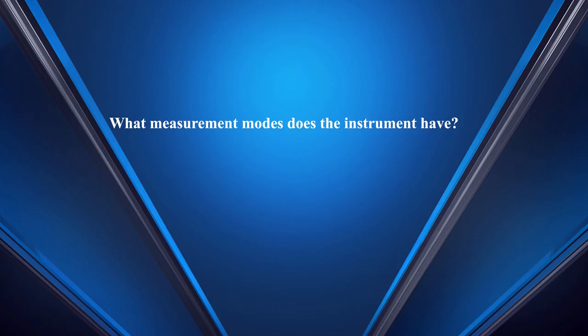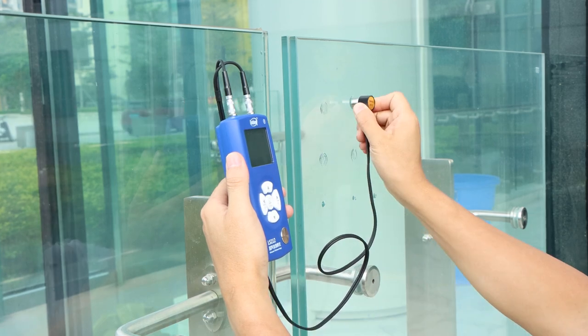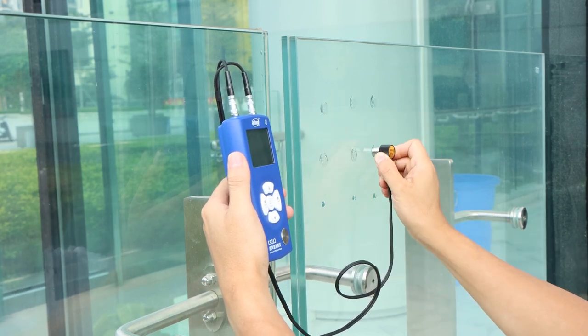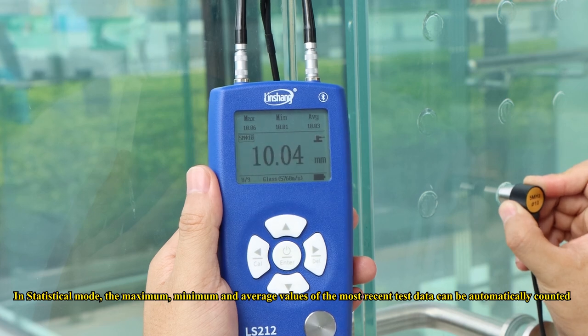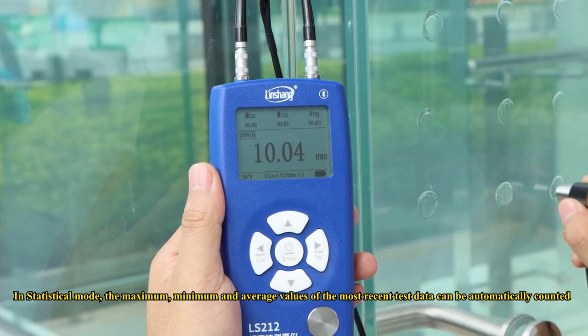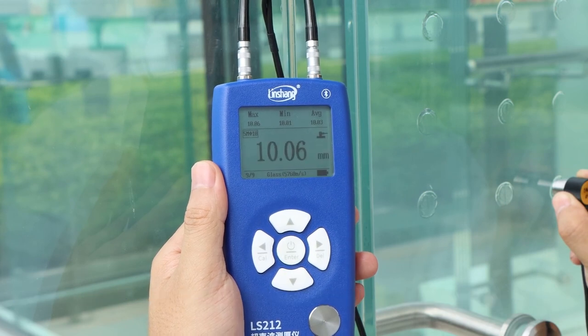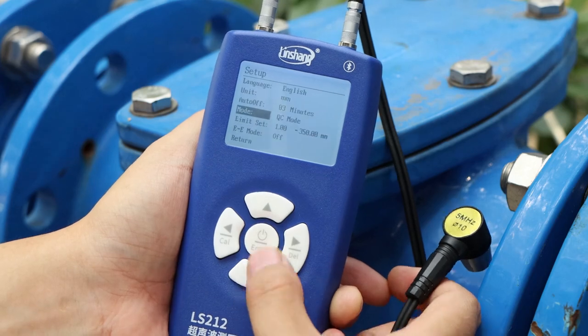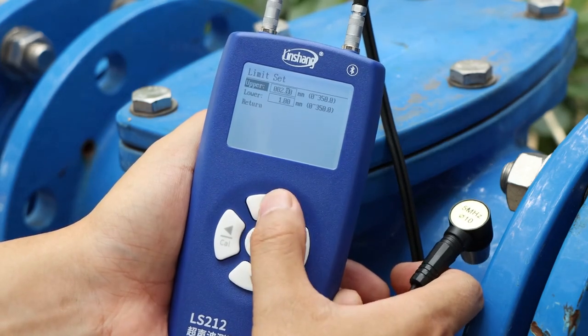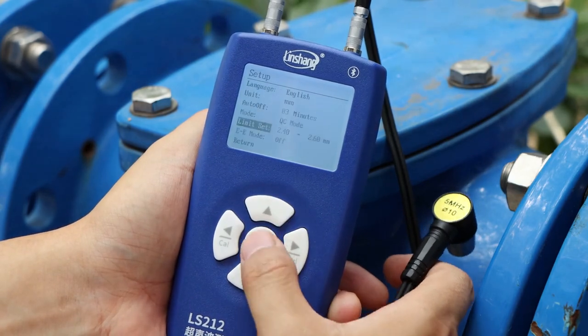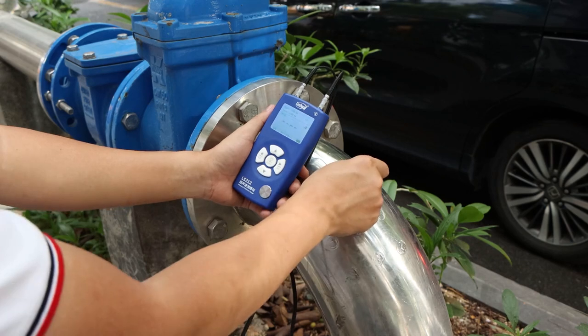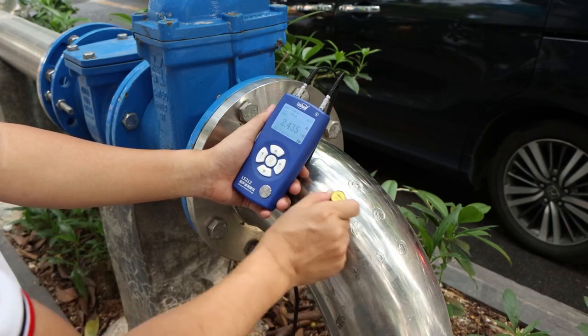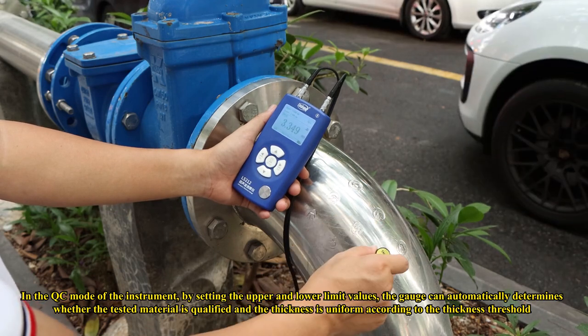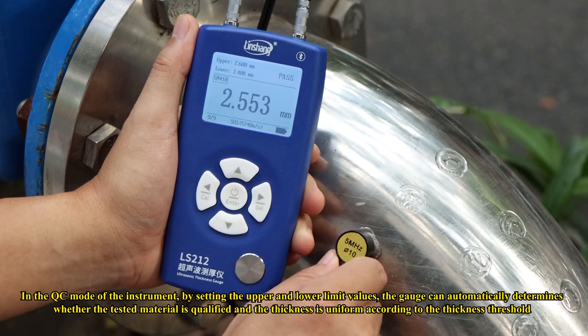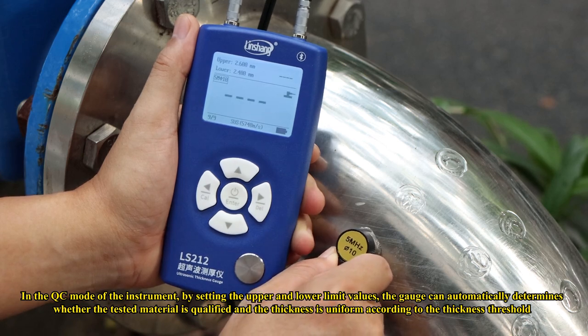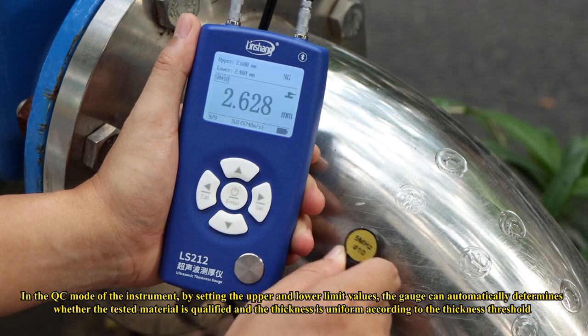What measurement modes does the instrument have? In statistical mode, the maximum, minimum and average values of the most recent test data can be automatically counted. In the QC mode of the instrument, by setting the upper and lower limit values, the gauge can automatically determine whether the tested material is qualified and the thickness is uniform according to the thickness threshold.